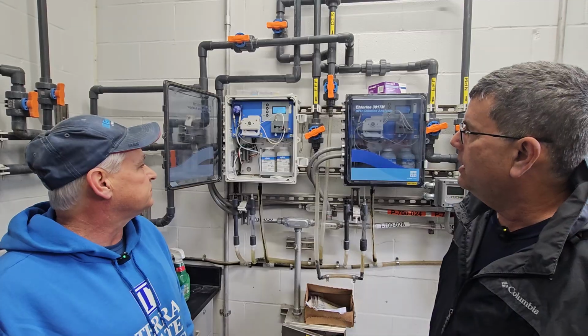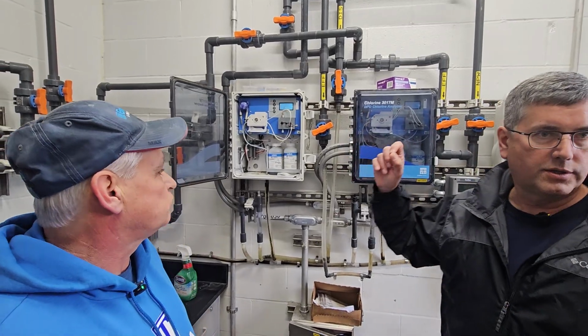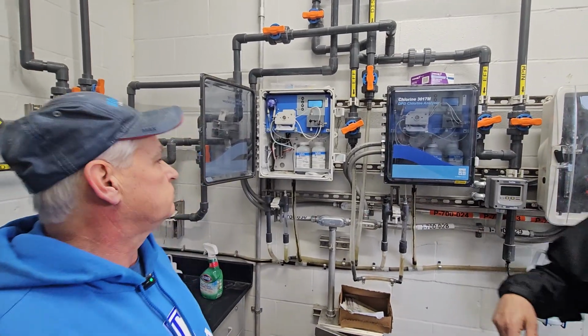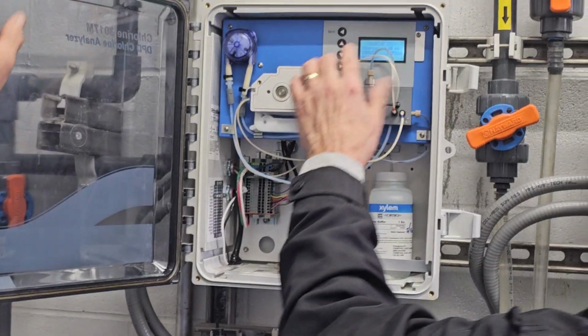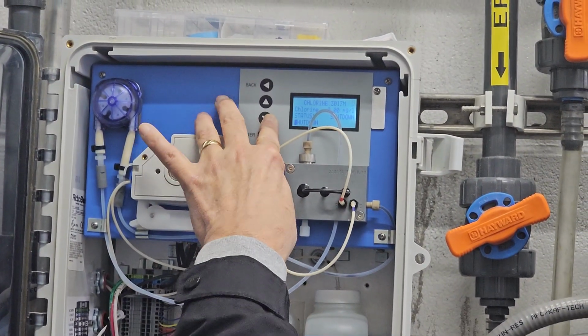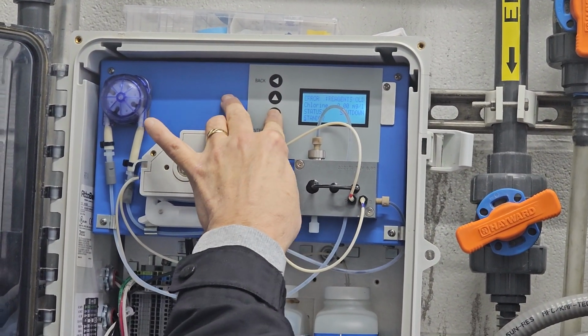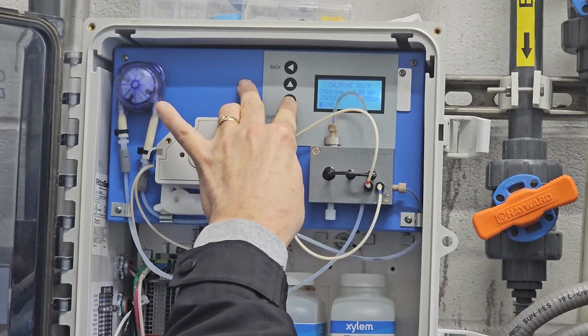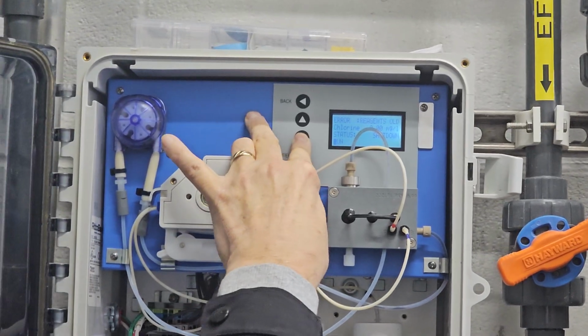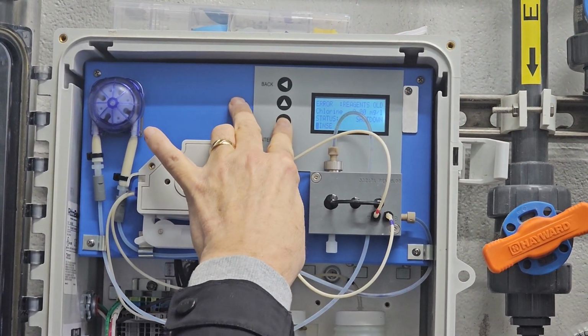So probably demonstrate how you get to running versus what you called standby mode. Yeah, but there's a startup. So you've got your modes: status, a bunch of modes. You've got shut down, standby, prime, run, calibrate, rinse.